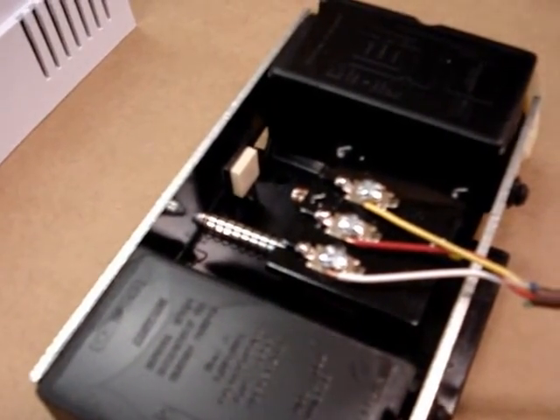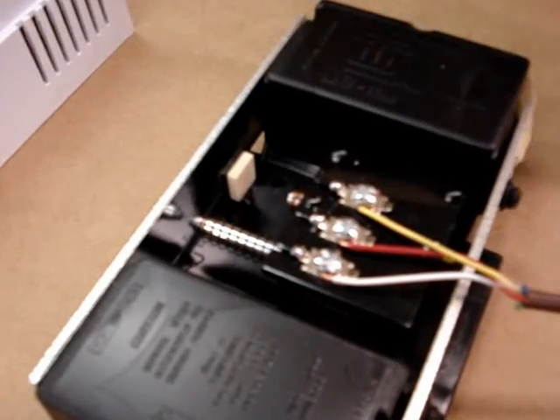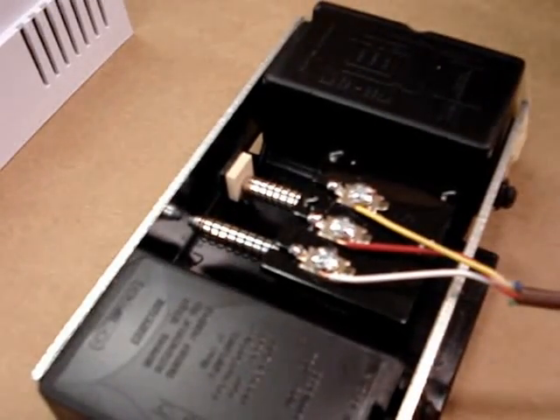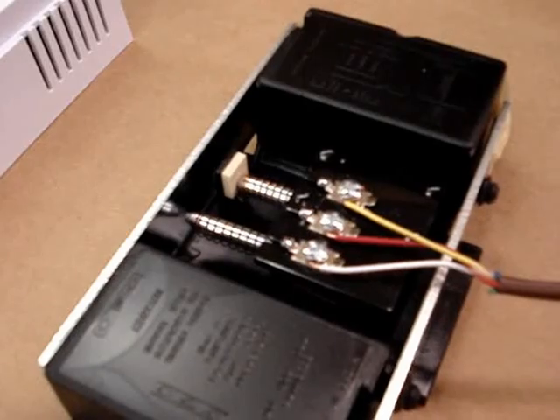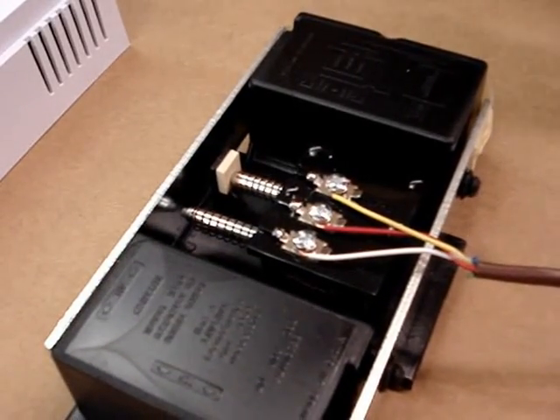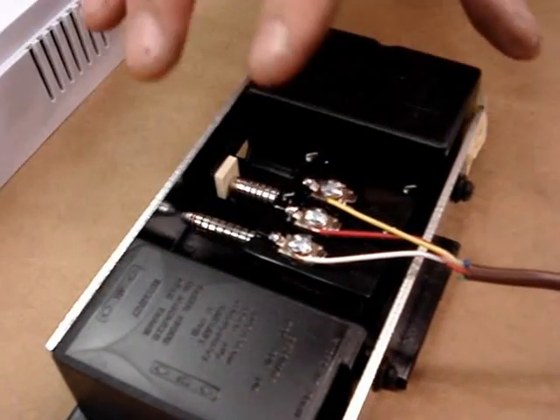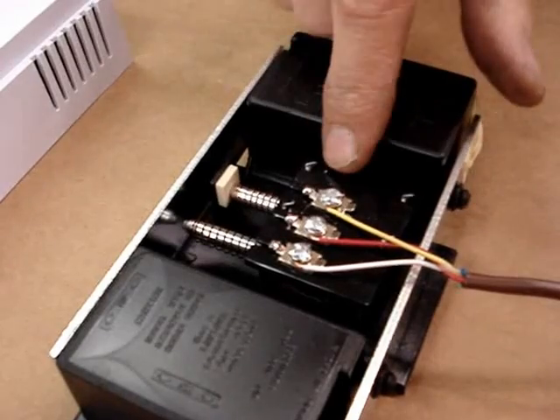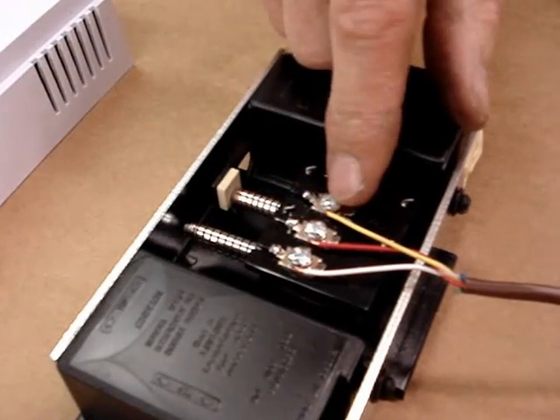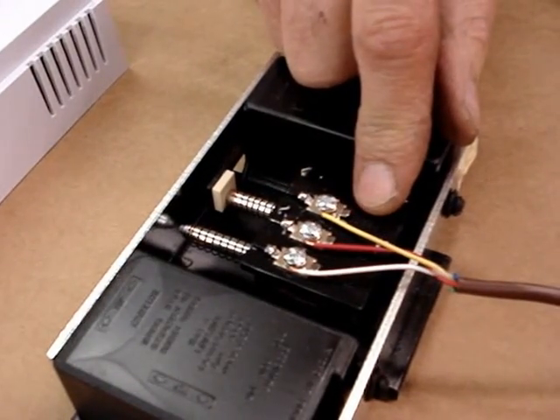If this doorbell button shorted out and stayed this way, after a while either the doorbell will burn up or the transformer will go bad. So if you have a dead short in the line, sometimes when you come to the doorbell you can see something's gone wrong, or even see that it got burnt from receiving power too long.